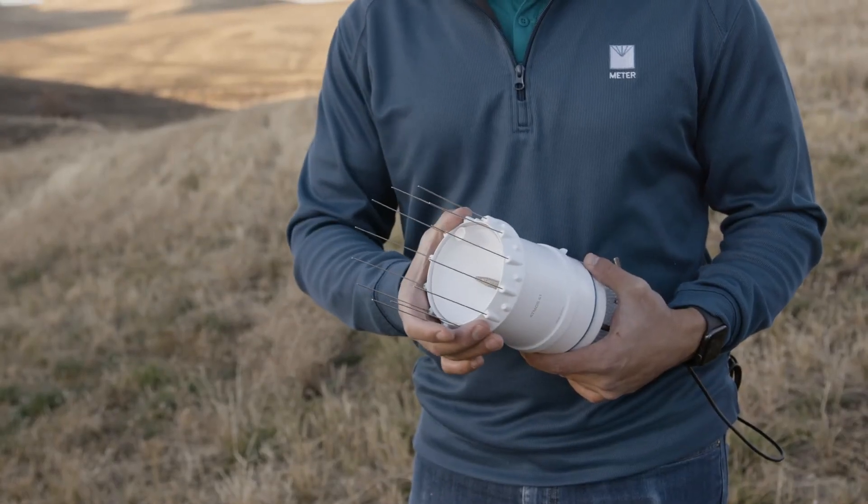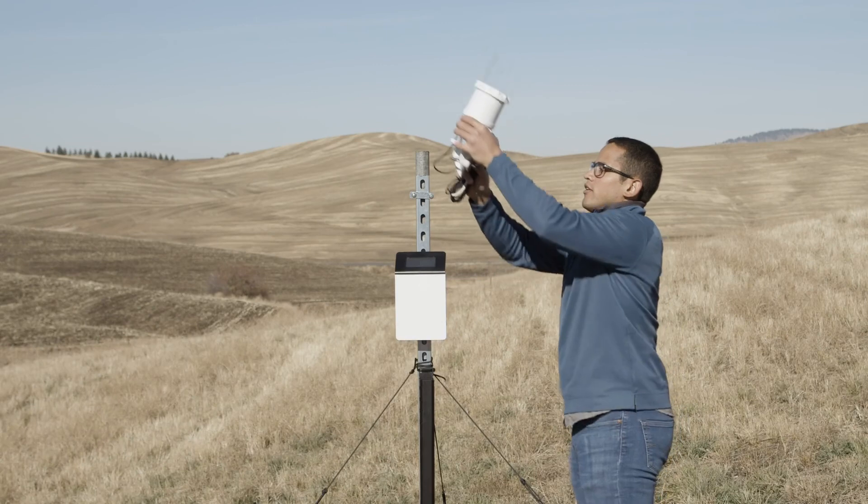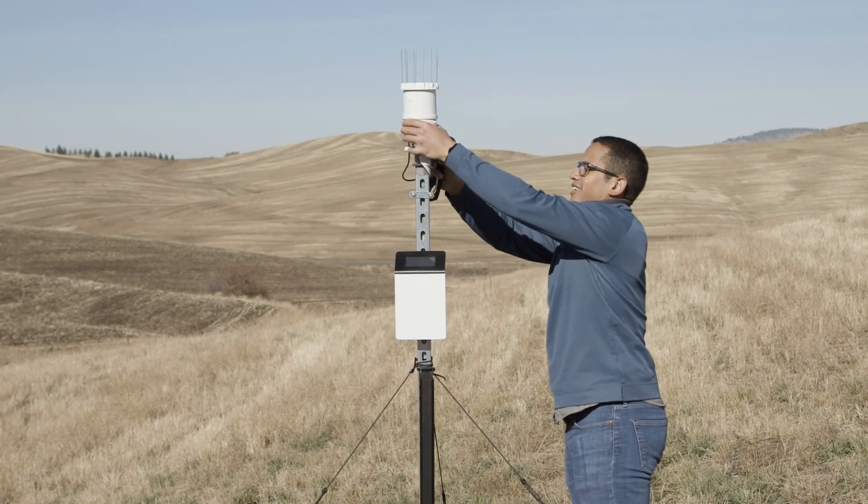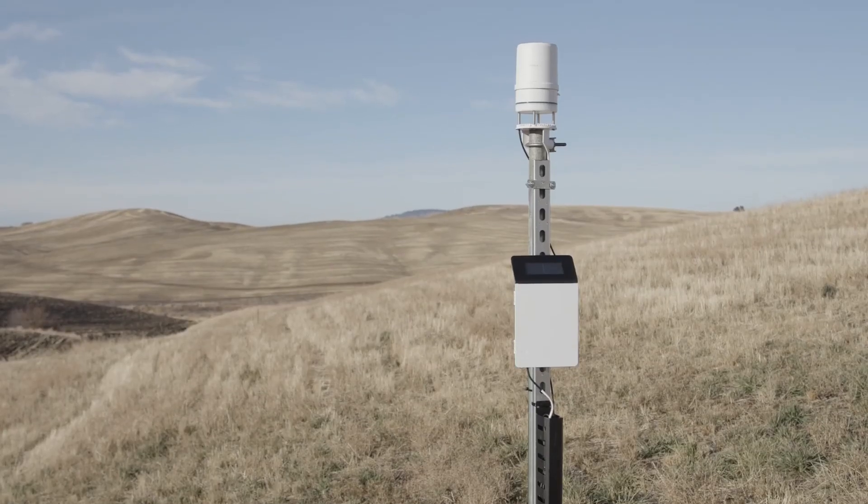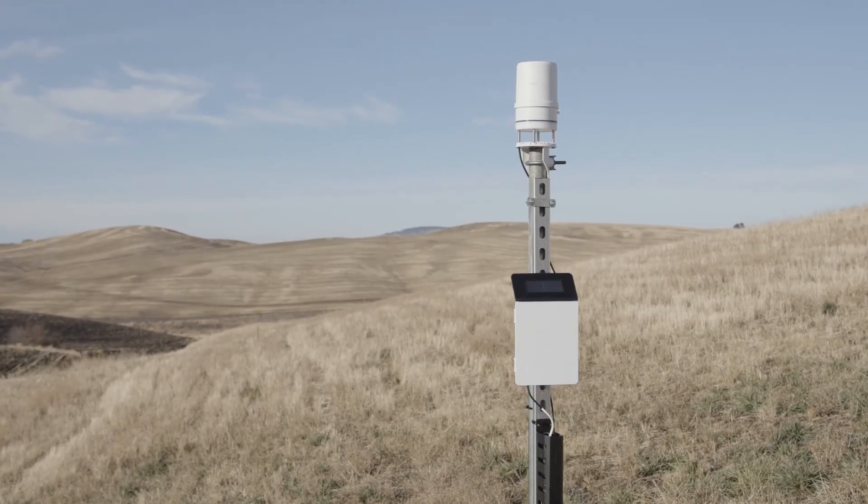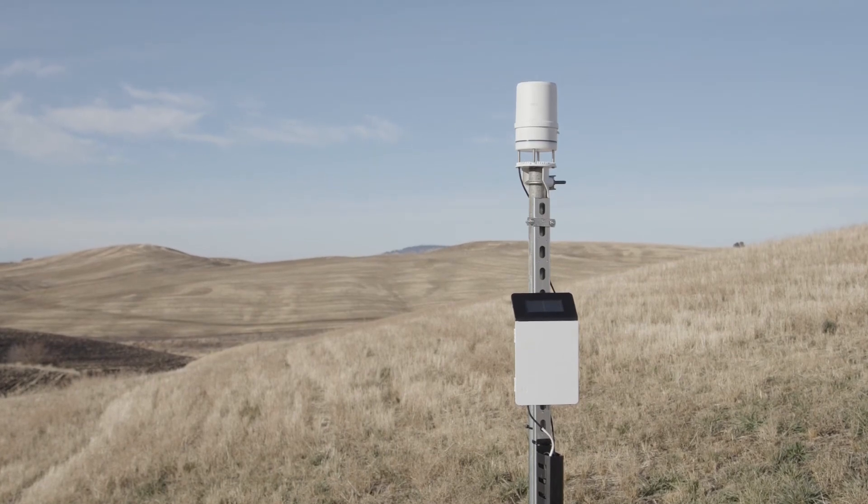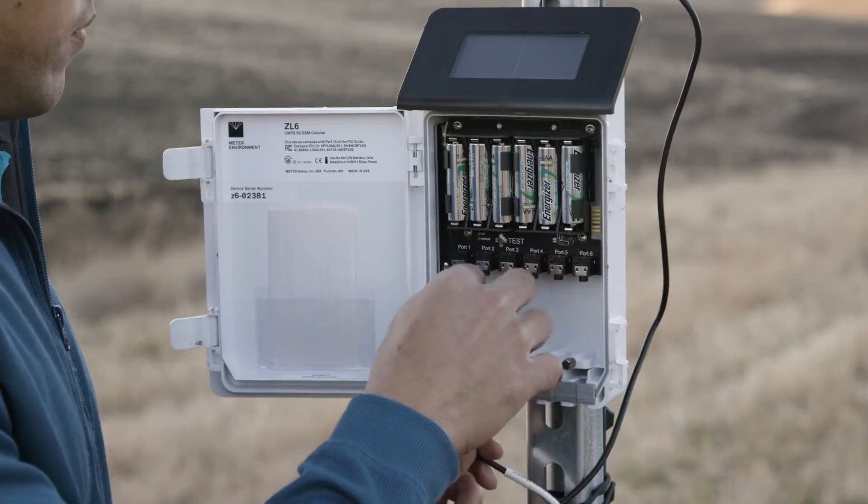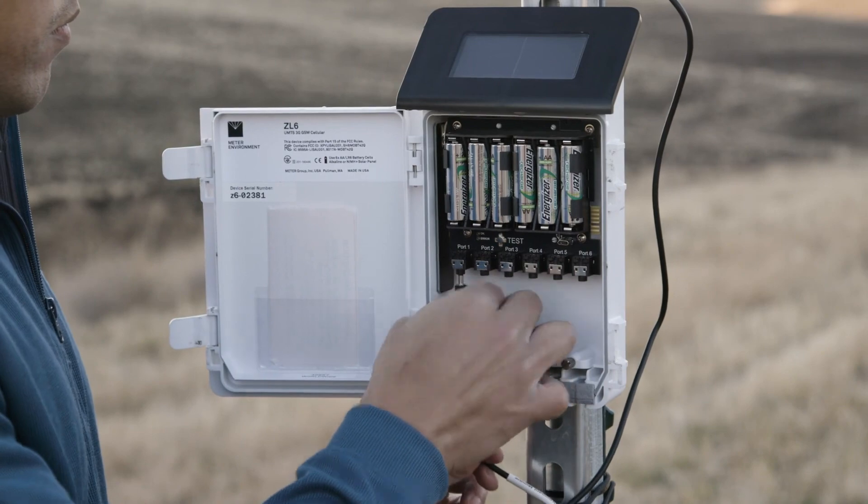When done cleaning, reattach the bird deterrent. Mount the Atmos 41 and level it. The Atmos 41 must be within approximately plus or minus two degrees of dead level, zero, zero, in both the X and Y directions to accurately measure rainfall and solar radiation. Reconnect the Atmos 41 to the data logger.